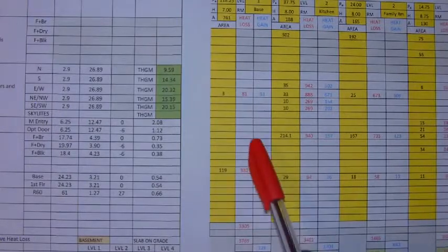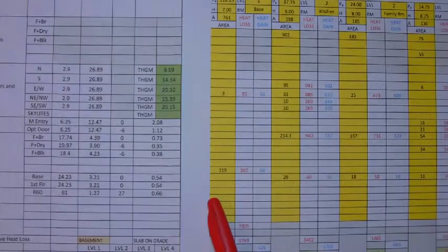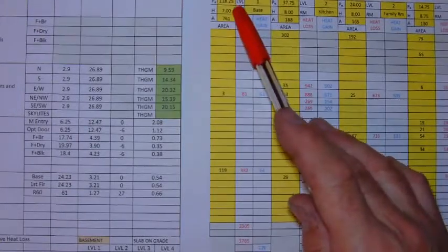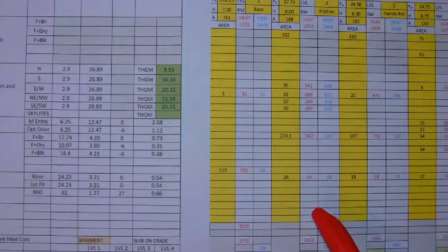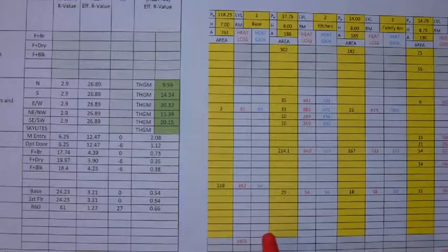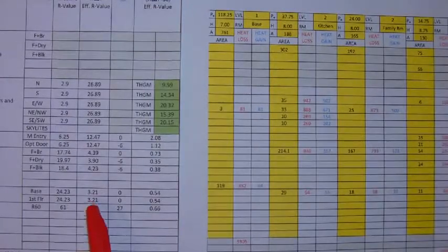Since we have no exposed walls, we do have to consider our basement header. In the case of the basement header, the header has been established to be 1 foot high, and so you take the total exposed perimeter, 118.25 feet, times 1 foot high, and that would give you 118.25 square feet. However, for our calculation sheet, we only work in whole numbers, so you would round that up to 119 square feet.